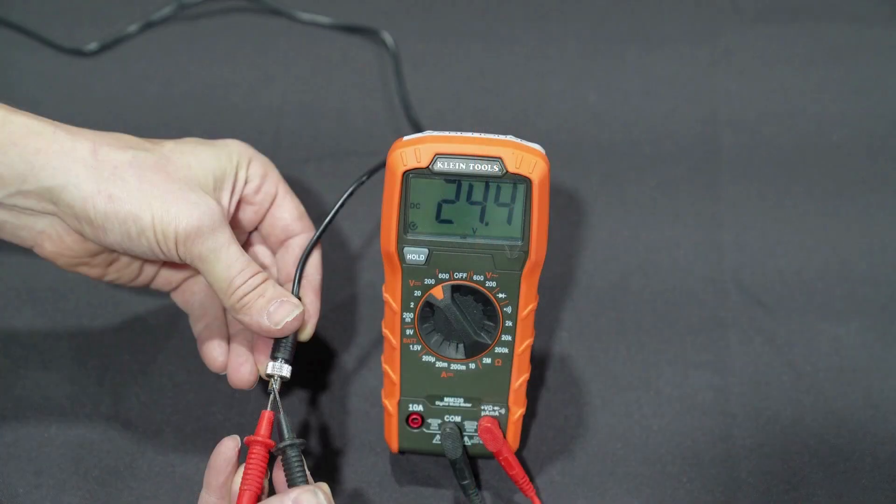The multimeter displays correct polarity and voltage, 24 volts give or take 0.4, indicating a good splice.